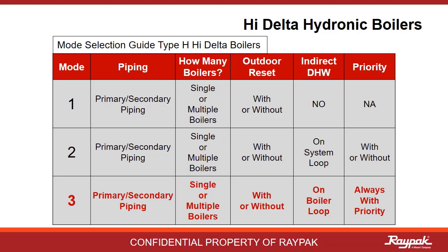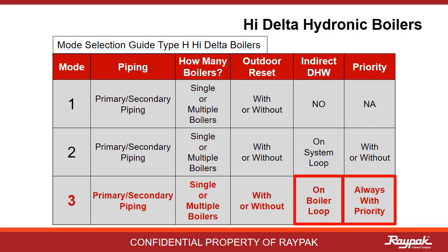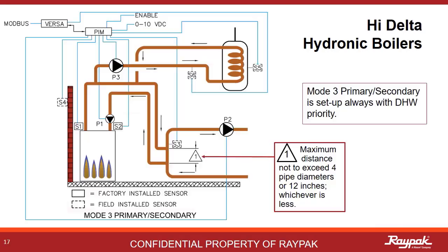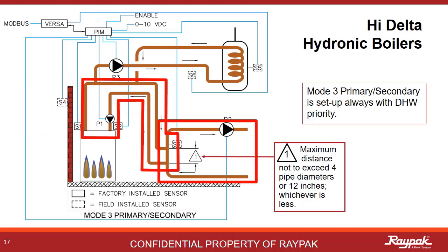Now moving on to the Mode 3 discussion. In Mode 3, the indirect domestic hot water is on the boiler loop. Mode 3 systems are always run with priority. Here is a Mode 3 primary-secondary single boiler system. You have a boiler loop and a system loop, and the indirect domestic hot water heat exchanger is on the boiler loop in this case.